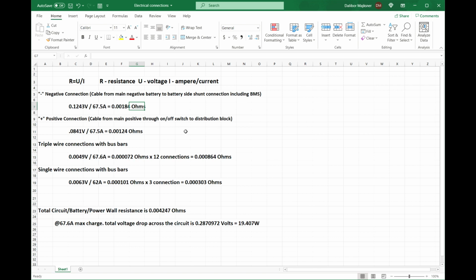For the positive connection, that's a cable from the main positive connection through the on-off switch to the distribution block up in the wireway, it is 0.0841 volts at 67.5 amps, or 84.1 millivolts at 67.5 amps. The resistance in that part of this circuit is 0.00124 ohms. All right. Now, the triple wire connections with the bus bars, there are 12 of them. Per single connection at 67.6 amps, we have a 0.0049 volt, or 4.9 millivolt drop, which gives us 0.000072 ohms of resistance per single triple wire connection with the bus bars.